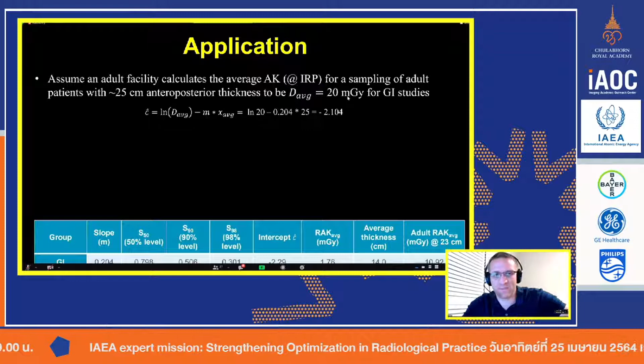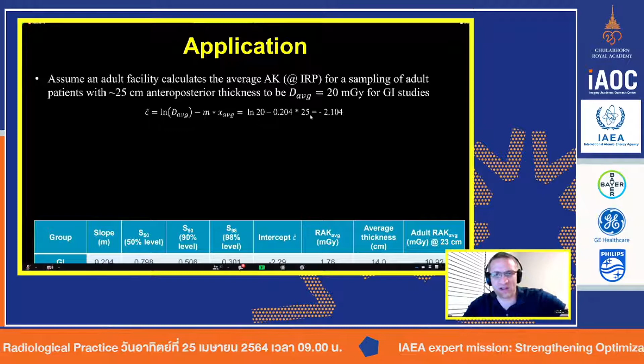And the M value comes from right here. X average is their average patient thickness, 25 centimeters. So I do the calculations, and it comes up with a scaling factor of negative 2.104. Now I want to create an alert level at the 98th upper prediction level. That means the 1%. Remember, if you think of a bell curve, you've got 1% here, 1% there. So we're thinking 1%: only 1% of all data would trip or trigger this level.